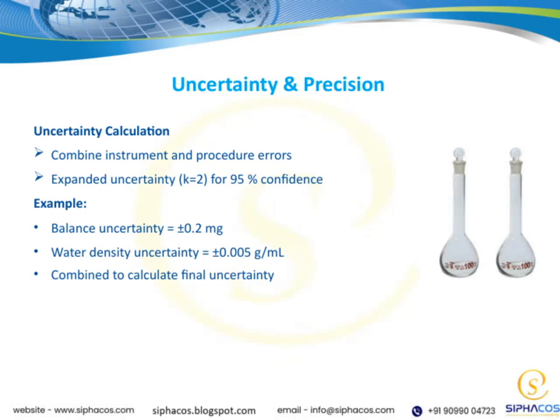Now, let's talk about uncertainty and precision. When we perform measurements, there's always some level of uncertainty involved. To handle this, we calculate the overall uncertainty by combining the errors from both our instruments and procedures. This way, we get a more realistic picture of how precise our measurement really is. We often use what's called expanded uncertainty, with a coverage factor of k equals 2, which gives us about a 95% confidence level. This means we're pretty sure that our true value falls within this range.